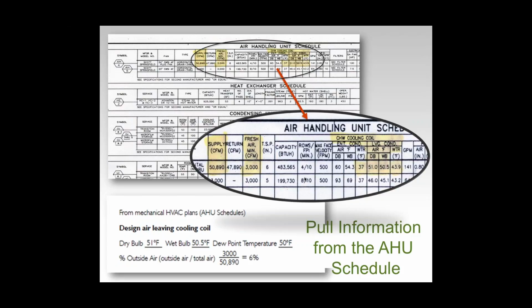Now this could be a little bit tricky. Your design drawings may go back to 1965 or they may only be 4 or 5 years old. But as we go through and start looking at these AHU schedules, we realize this is where some of that critical information about how the system actually runs sits. It's where it lives. And as we go through and find out, well, here are my entering conditions and leaving conditions off of the cooling coil, and there's water temperature. But in this particular case, if I want to know what that coil is designed to do, well, what's the leaving air condition?